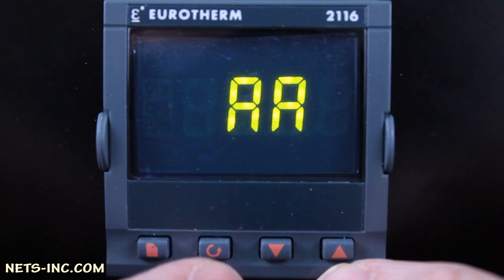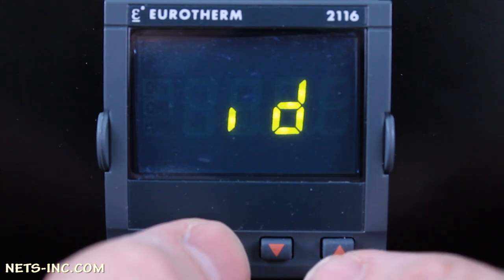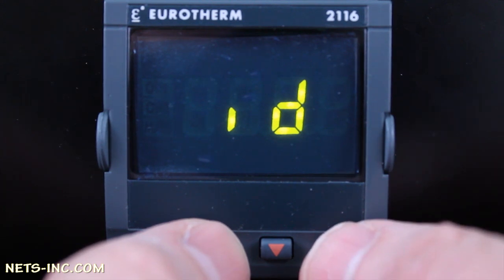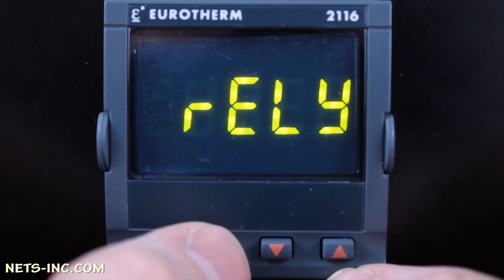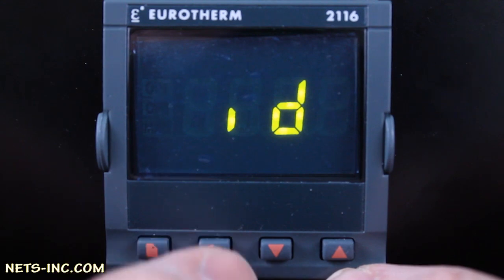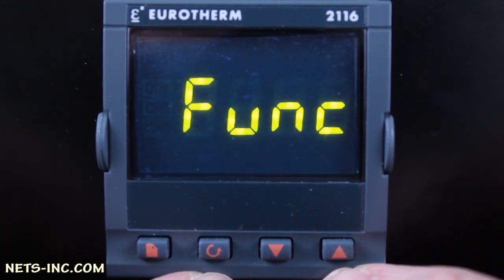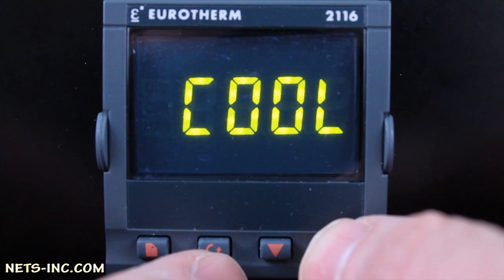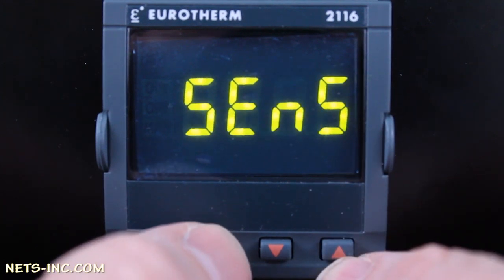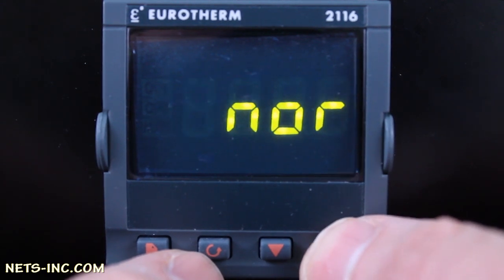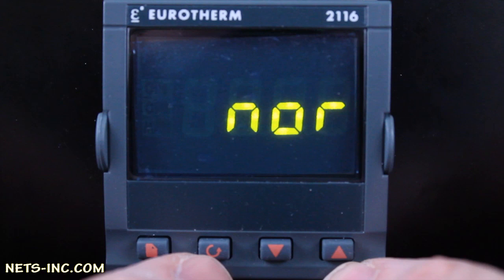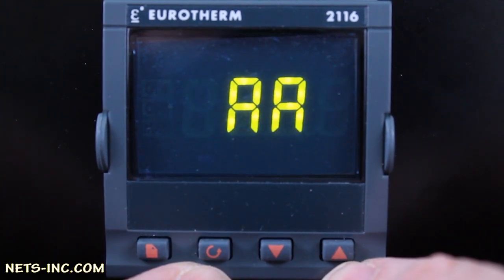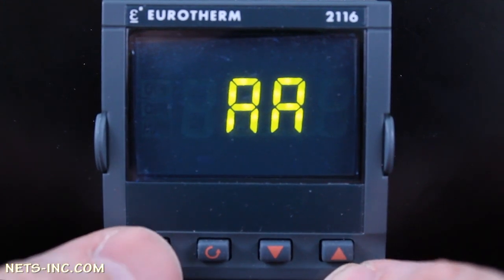The AA list corresponds to the relay output on terminals AA and AB — this output will be set up as the cooling output. Press the Scroll key once to drill down into the AA list. The display will read 'id'. Press the Up Arrow to verify that ID equals RELY, or relay. Press Scroll once and the display will read FUNC. Press the Up Arrow repeatedly to change FUNC to COOL. Press Scroll and the display will read SENS, or sense. Press the Up Arrow to ensure the display reads NOR for normal. Press Scroll once and you are back to the display reading AA.